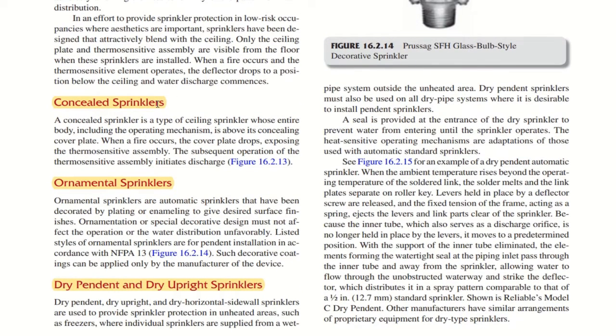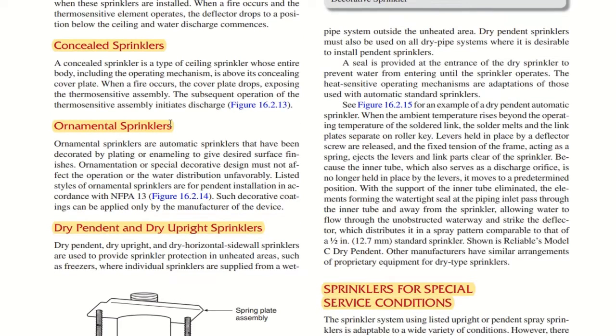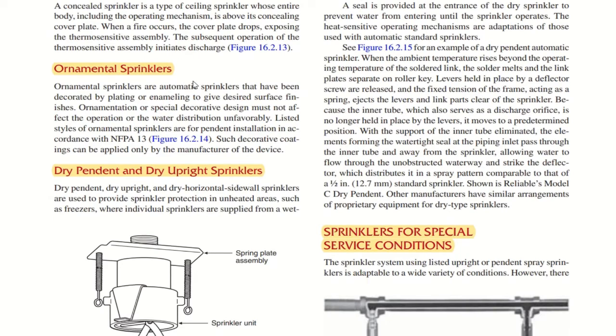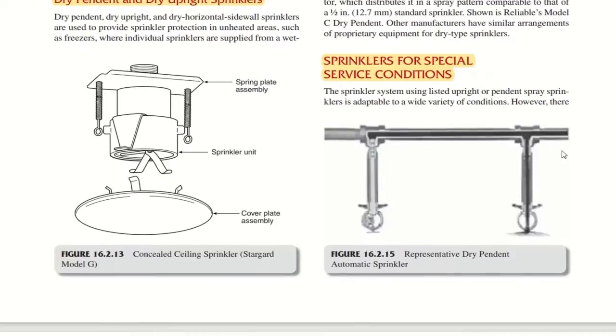Here you have concealed sprinklers. So pendant sprinklers, they are also called pendant sprinklers, however these are concealed type sprinklers. A concealed sprinkler is a type of ceiling sprinkler whose entire body including the operating mechanism is above its concealing cover plate. I think you can understand easily, since you are appearing for the certified fire protection specialist exam. It means you definitely have an idea about all these types of sprinklers. You have various other sprinklers such as ornamental sprinklers. They have been decorated by plating or enameling to give desired surface finishes. You have dry pendant and dry upright sprinklers as well.